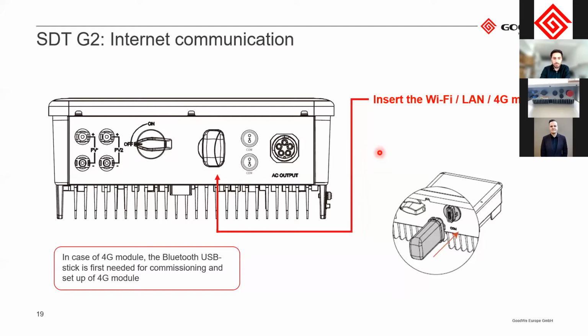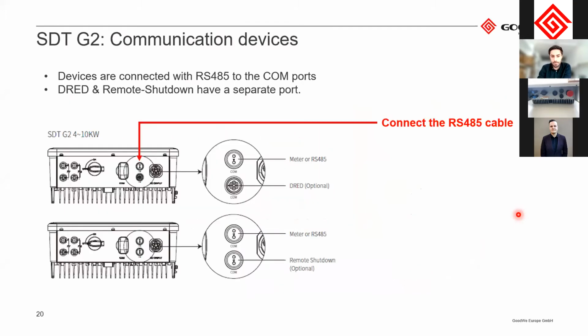For the communication module, as I told before, you have some different communication modules, either Wi-Fi, LAN, or 4G. If you use 4G, you will need a Bluetooth module to commission the inverter. But basically on the SDT G2 inverters, it's quite easy. This is just a USB port. The module is also USB compatible, and you just push it right in and it will work.